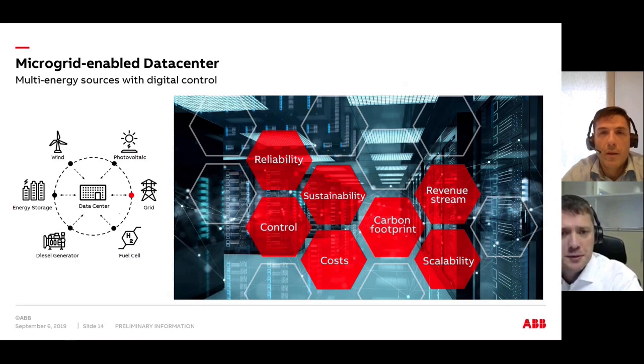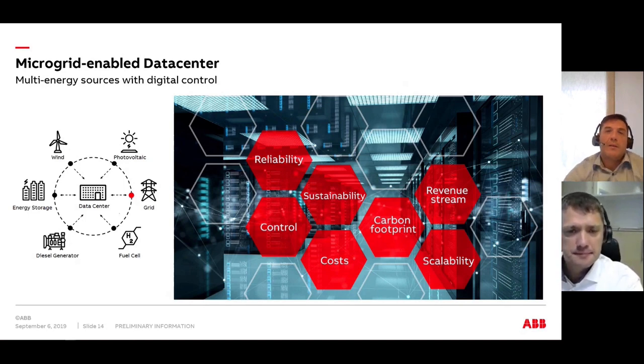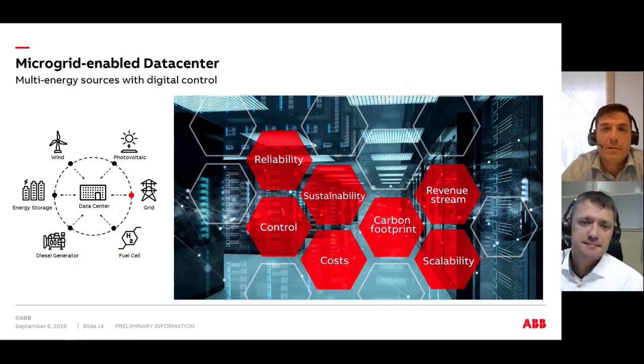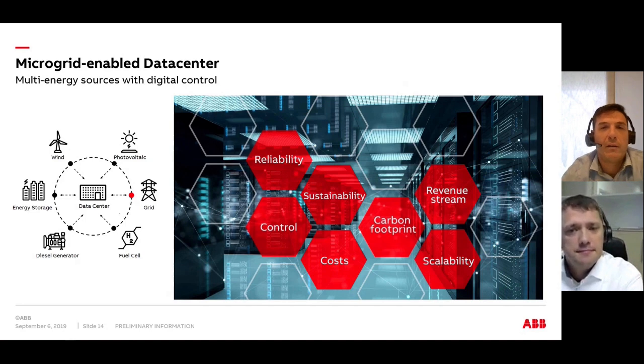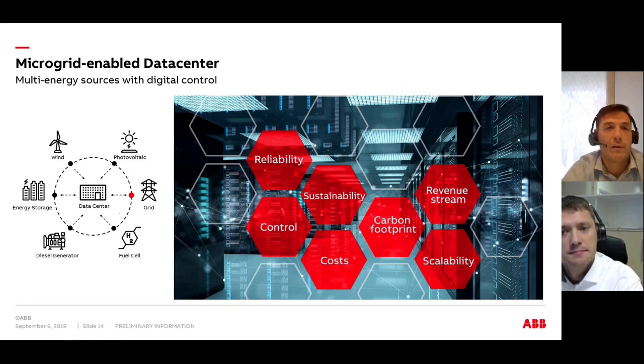Very good. Let's take another most important element from this formula, the sustainability. Can you elaborate a little bit on this one? Yeah, very good, Daniel. On the sustainability, regardless of the steps taken to use more efficient equipment and to conserve energy within a data center, the challenge that remains is the transition to clean, renewable energy. That's the key. This transition is enabled by a microgrid architecture that is going to control the energy mix within the facility through renewable on-site generation, but always coupled with battery energy storage to optimize efficiency. We want to use the energy coming from the renewables in the most optimal way. The capacity installed in a battery energy storage integrated within the microgrid of a data center is going to provide the needed backup power without starting the gensets immediately after a grid outage, or, as we saw, they can even replace gensets.